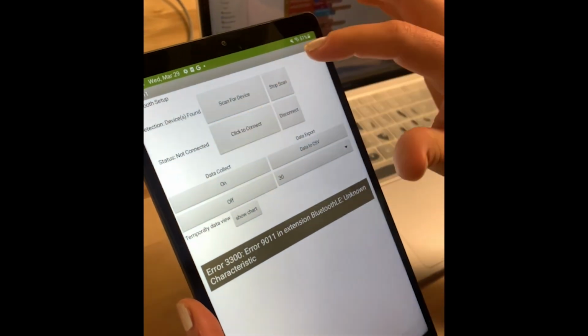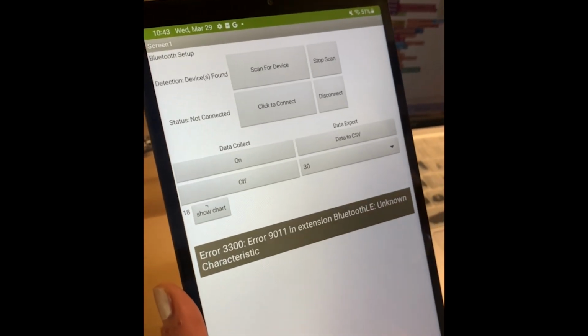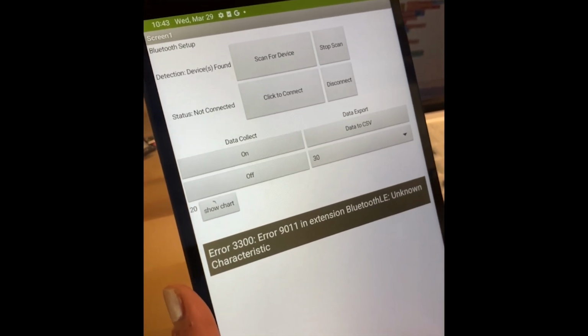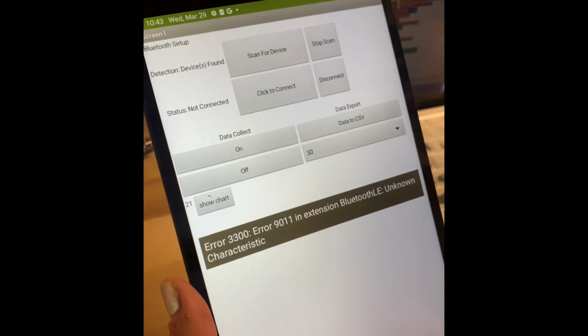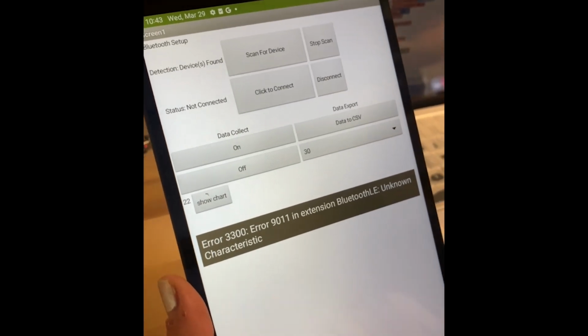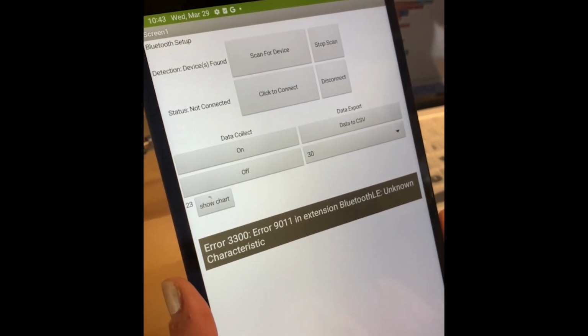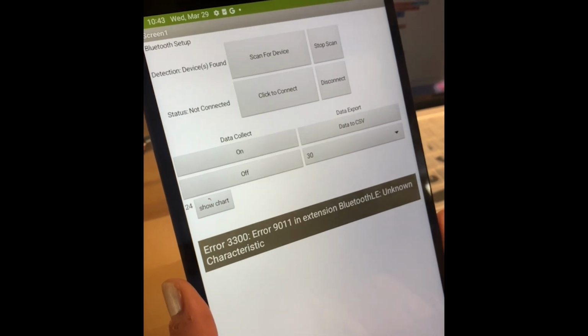Through MIT App Inventor, we were able to establish a secure connection to the Bluetooth Low Energy module on the ESP32, attached to the retractor system, by identifying the correct MAC address associated with the ESP. Using the device address prevents the accidental pairing of a different Bluetooth device, and the Bluetooth Low Energy capability decreases the power consumption of the system and limits the heat produced by the circuitry.